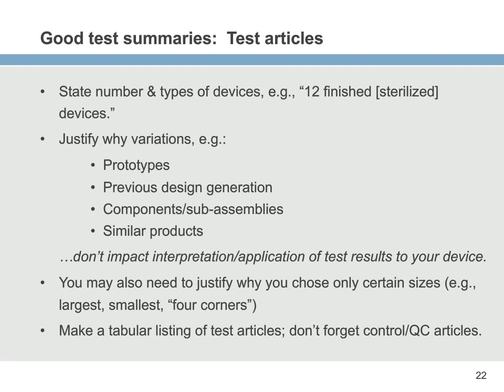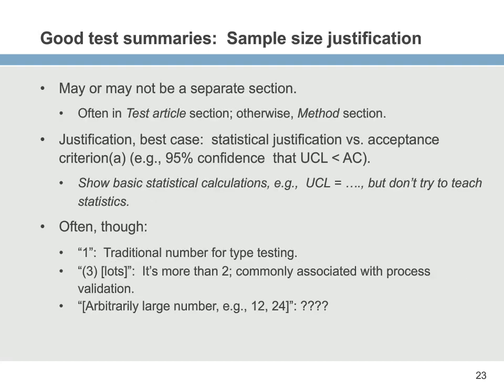So you'll sometimes have to justify why you choose only certain sizes. So if you've got a variety of lengths and diameters, you'll choose the 4 corners. And sometimes that gets to be a paragraph long. And again, it may not be in the test report, so you've got to describe it so that the test report gets received well. So sample size justification, again, may or may not be in a separate section. Sometimes it's just as simple if it's a sample size of 12 and 12 is somewhat arbitrary, just hook that up with the test article section and be done with it.